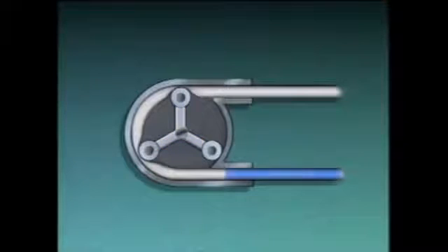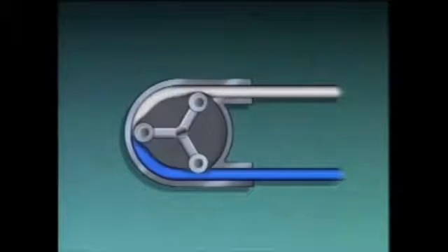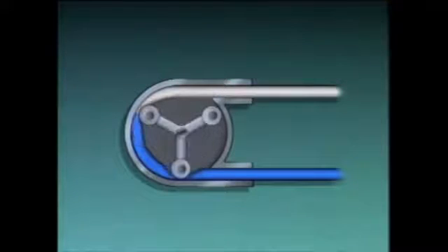During operation, liquid is drawn into the tubing at the suction of the pump. The rollers turn with the rotor and compress the tubing, trapping liquid inside. As the rotor continues to turn, the rollers force the trapped liquid through the tubing and out the pump's discharge. Tubing pumps normally don't have as high a flow rate as other types of rotary pumps, but they're often used as sampling pumps for corrosive or toxic liquids, since the liquid doesn't come in contact with the pump's components.